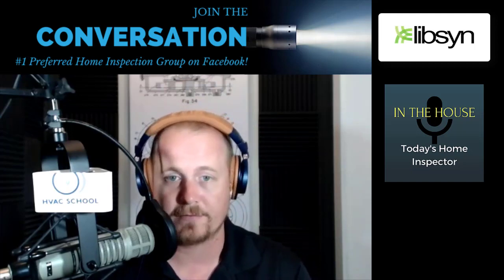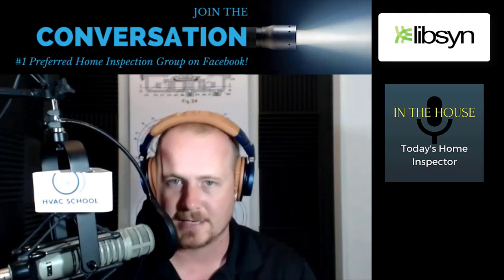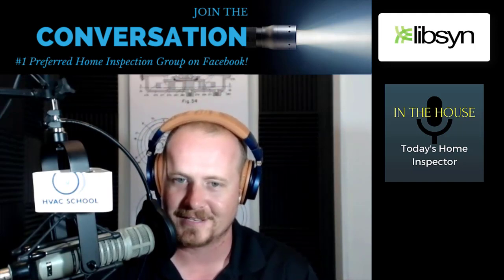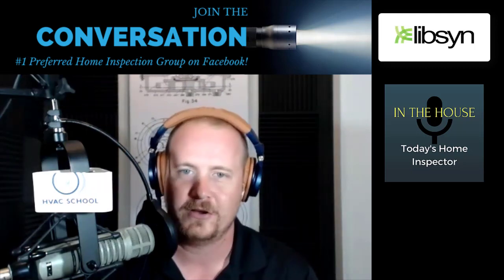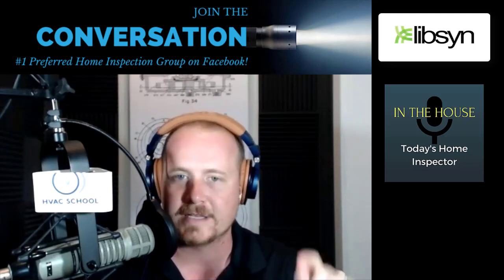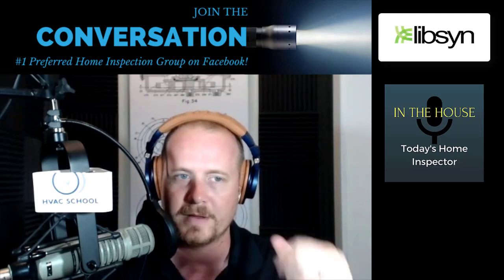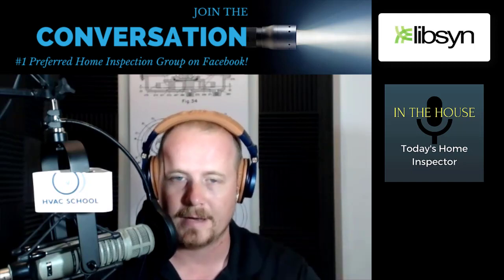And on most of this equipment, you're going to find where somebody's used a dry bulb probe previously. A big piece of this, and I understand this because my father was a home inspector for a while, is that you don't want to be invasive. You don't want to do anything that anybody later on is going to say your license didn't allow for, or that you broke it. So you got to be really careful. You don't want to take anything apart that you don't need to. That's right. But in most cases, there's going to be a little point prick penetration where somebody's put a dry bulb thermometer in there before. And so the best thing to do would be to measure the temperature of your supply air as close to the unit as you can get.